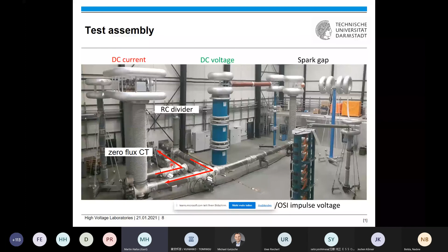So why did we choose DC current? Our goal is 3050 amps at 660 kV DC. And when you keep in mind that we have a 100-meter loop, you have to consider that an AC current also will need some reactive power. When you check the numbers for AC current and DC current, you will see that AC current heating for our loop would need in the range of 150 kilovolt-amps reactive. So you need test generators with this rating, so a lot of current transformers inside the loop. On the other side, as active power you only need 10 kilowatts for this long loop. This is not very much. So you see it's a very efficient solution to use DC current to heat the inner conductor.